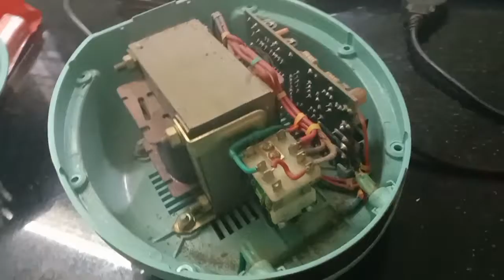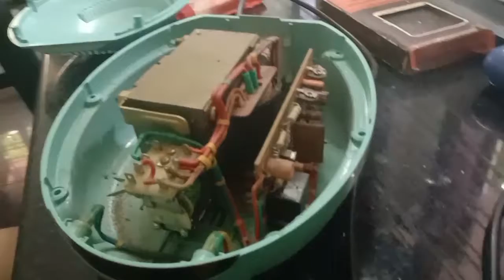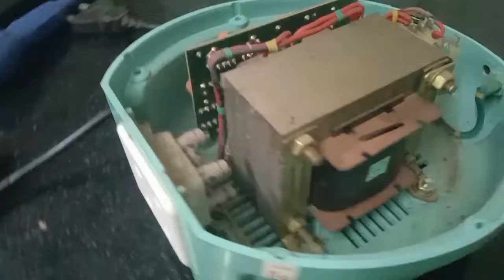The major components of the stabilizer are the transformer and the PC board. The fault can occur if a high voltage is passed through the stabilizer. It can get heated up and many components can get damaged, and it can also decrease its performance if the lamination gets deteriorated in the transformer.